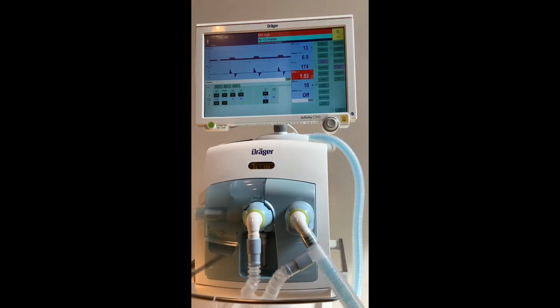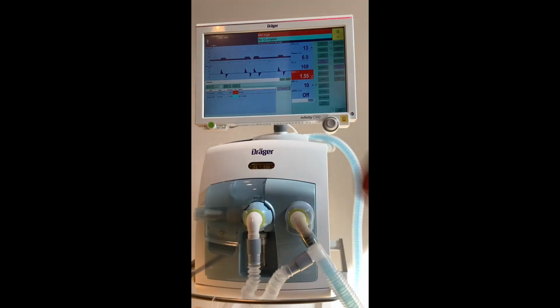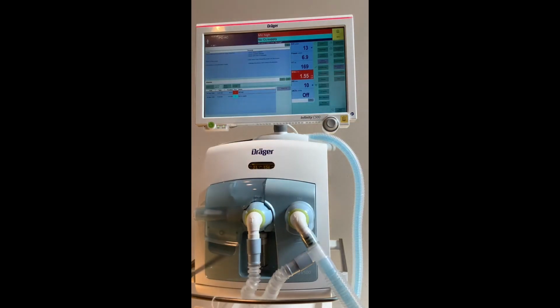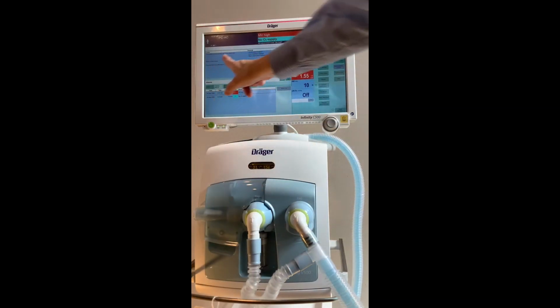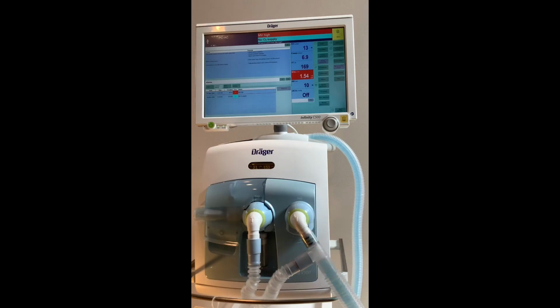To troubleshoot your alarms, it's very simple. Simply touch the message displayed on the screen, the ventilator will give you a listing of all of the active alarms. Highlight any one of them and use the up arrow to get a description of the potential causes and remedies for that alarm.